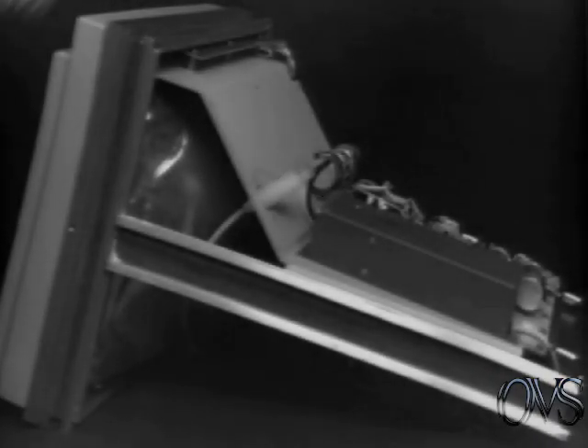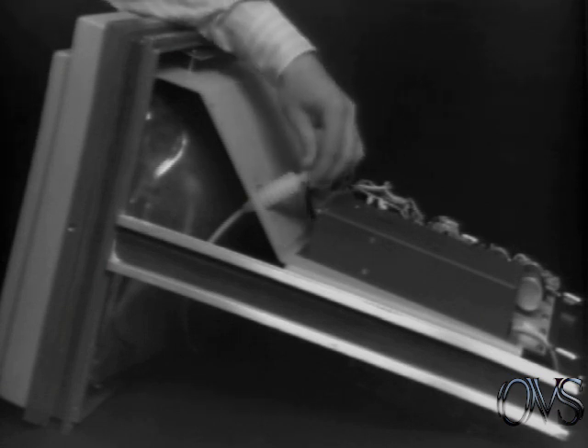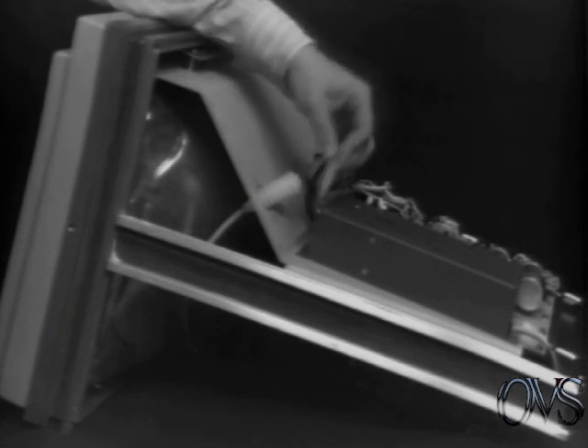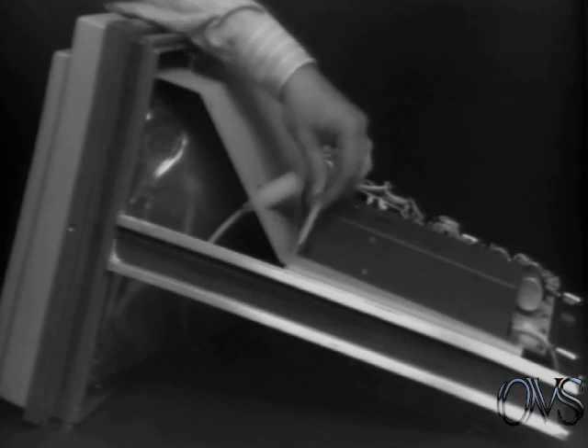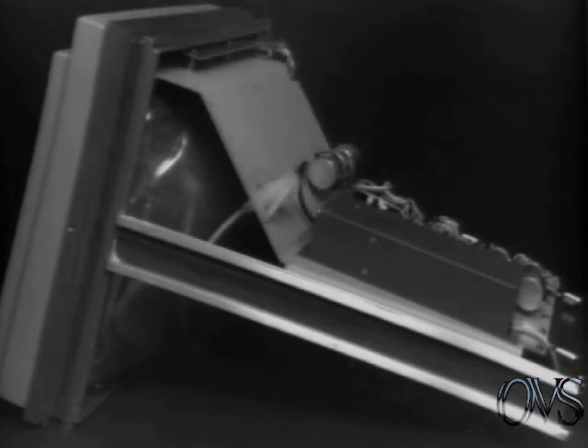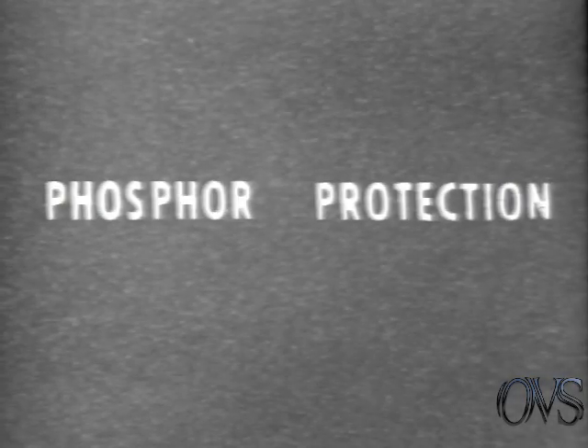Your answer should have been, discharge the post-accelerator lead to ground. This lead has 24 kV on it, and the power supply will hold this charge long after the power has been removed, unless it is discharged. Next, briefly explain the purpose of the phosphor protection circuits.